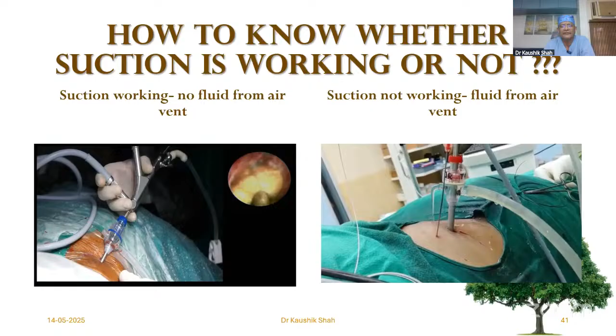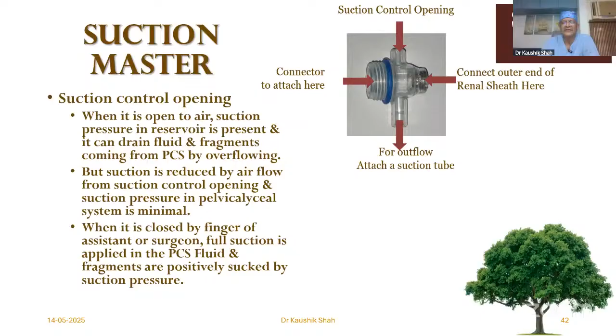Now coming to the suction control opening, this is the heart of it. This is designed to control the suction. If it is open to air, whatever fluid is coming into the reservoir is sucked, but minimal pressure is transmitted in the PCS system. So it becomes an open system. When you close it, it becomes a closed system, and all the pressure is transmitted inside the PCS system, and therefore just by a fingertip, you can activate the suction and close the suction. And the position is such that any assistant has free access to that suction control opening.